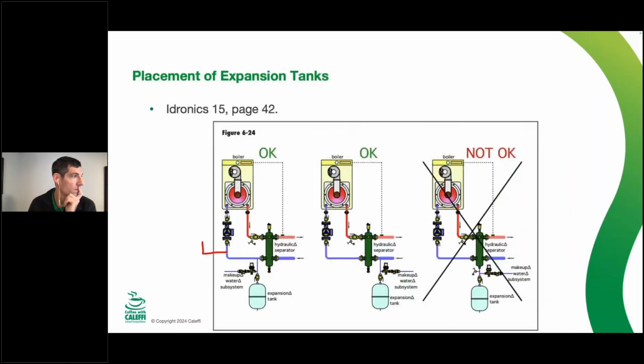So if you have an air vent on the suction side or on the return side of that system, you can in fact pull a sip of air in every time that circulator starts up. Then you get the call the system's noisy again, and you go back and you purge it, and it's fine for a couple of days, a couple of weeks, and you've got an air problem again. Look at the relationship of your pump to your expansion tank, and that's what you need to correct to stop that. And we've got a really good B&G drawing on that.